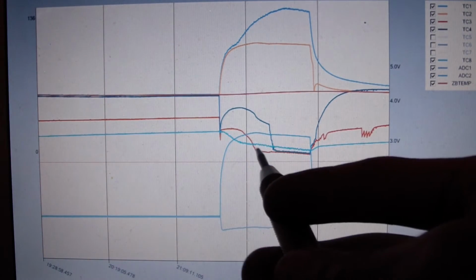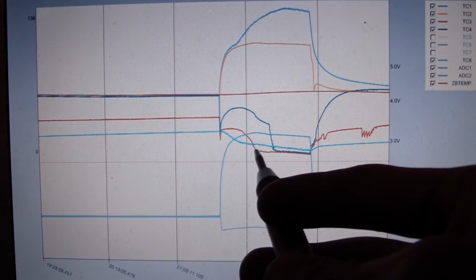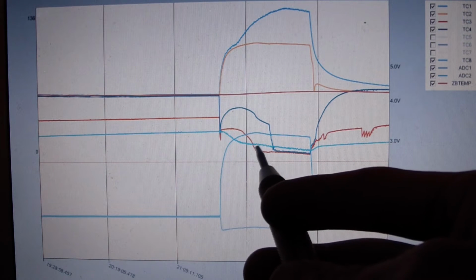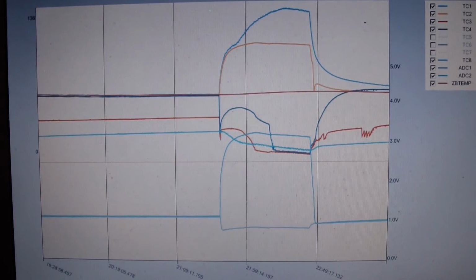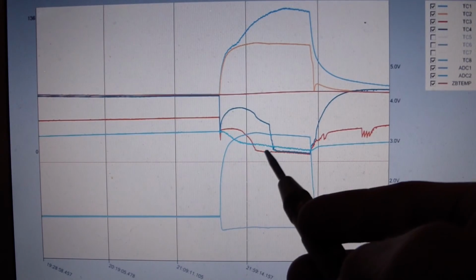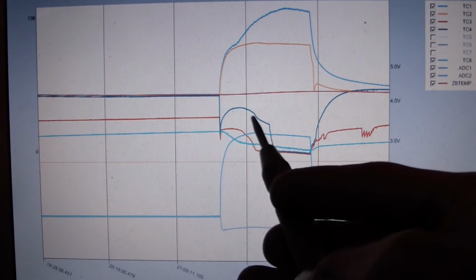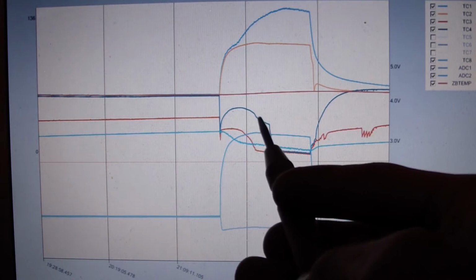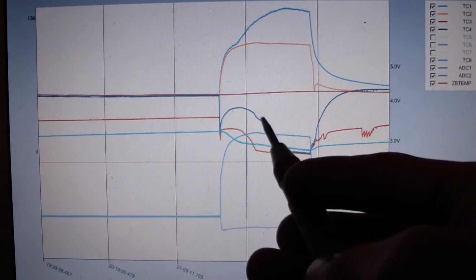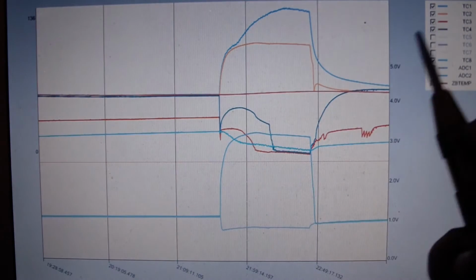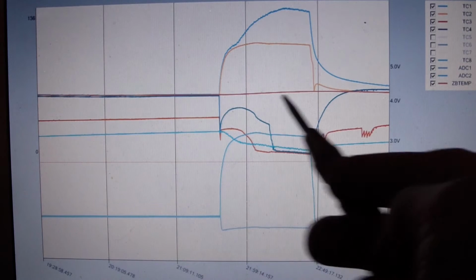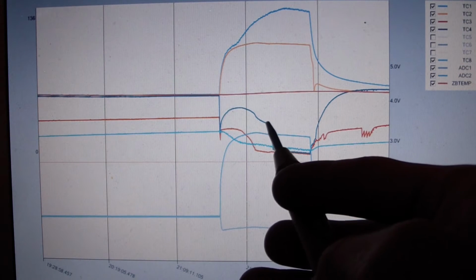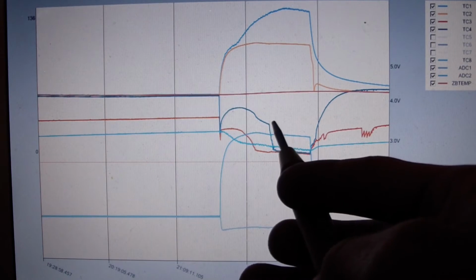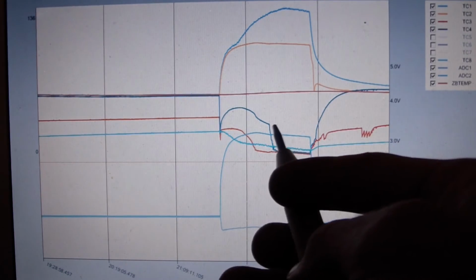Kind of the next interesting spot here is where the suction superheat after the evaporator finally more or less bottoms out. And just from observation and common sense, you can see this kind of flattens out and slowly drops. It's pretty much come down to saturation at that point. Also, right around that point in time, you see a change in the slope on the suction superheat after the heat interchanger as well. Things starting to change, and then you have this sudden drop off in the suction superheat before the evaporator, post heat interchanger.